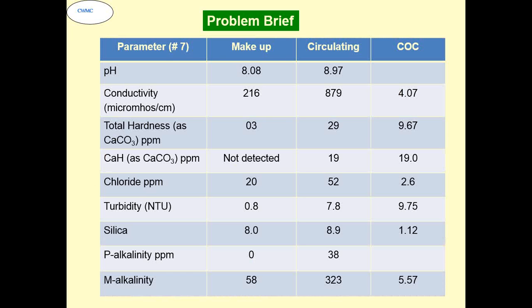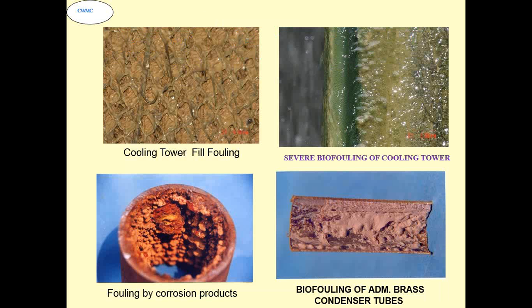These are the characteristics which were changed by the fly ash falling into the water. You can see the alkalinity, conductivity, everything changing because of the fly ash falling into the cooling water system. Now this is typical biofouling. What you see here is the cooling tower fill pack, totally packed. Water cannot flow through that. In other places you see thick algae. In the third picture, the pipe inside has lateral growth, so you can see how much water can flow because the diameter has already reduced, and apart from that there are frictional losses. The fourth is again typical biofouling, where the flow is reduced and the tubes are susceptible to microbiologically induced corrosion.